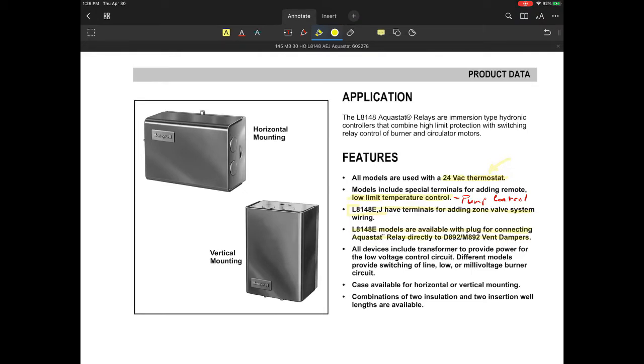Now, some of these boilers are, let's say, natural draft, category 1 natural draft. So I'm talking about your typical cast iron boiler. They may have an actual vent damper that will close when your heating demand is done. And so that's one way, or they'll do that if the boiler is no longer operating. So all of these devices have a transformer.